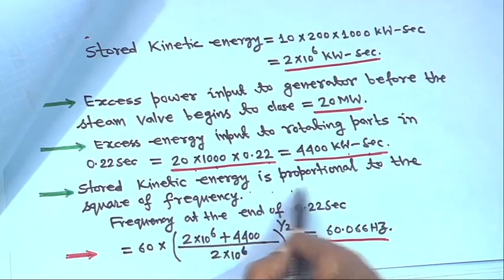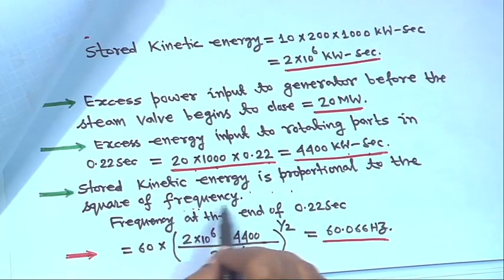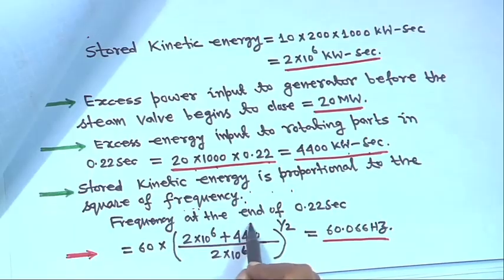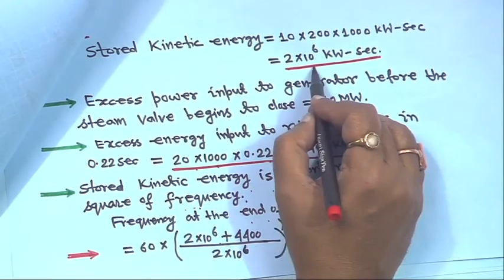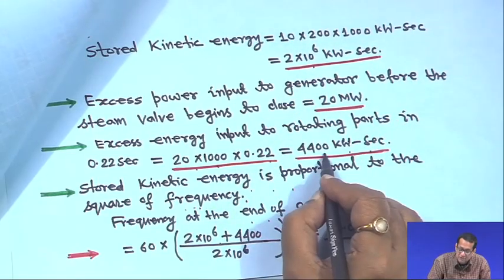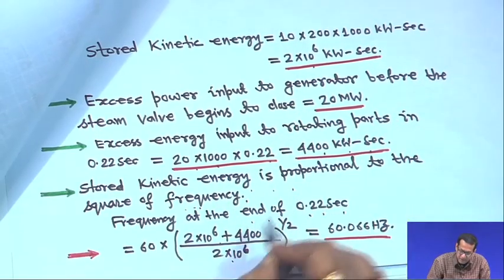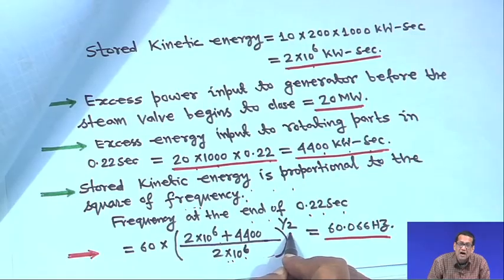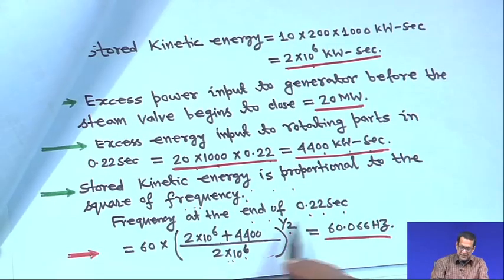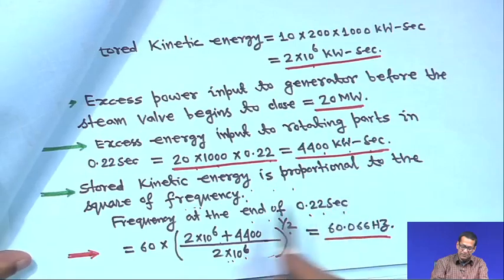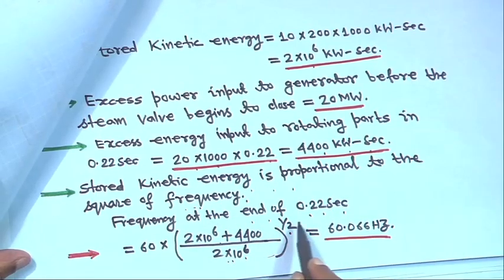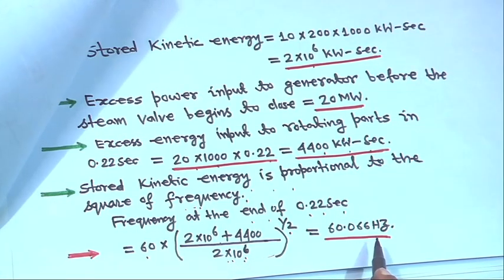Therefore, stored kinetic energy is proportional to the square of frequency. So the frequency at the end of 0.22 second will be 60 into 2 into 10 to the power 6 plus 4400, divided by 2 into 10 to the power 6, all to the power half, right? Because kinetic energy is proportional to the square of the frequency. Here 60 is the frequency, right? So it comes to 60.066 hertz, right? So this is the idea, right?